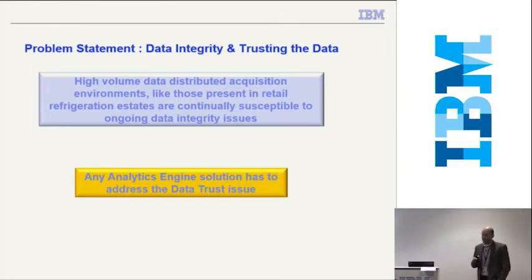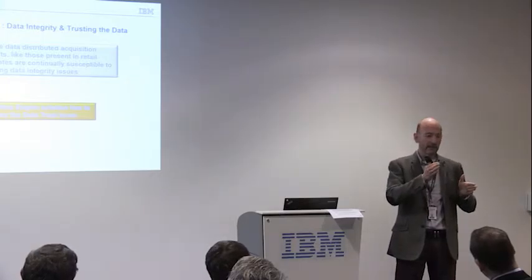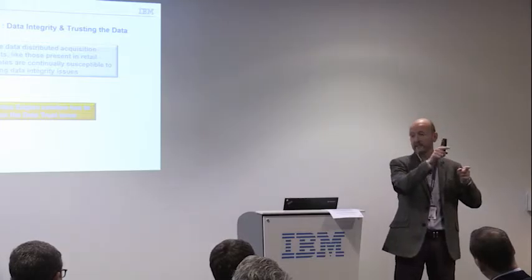Actually, one of the other things that we have as well, just on the data and data outage, another problem that we came across was when you have missing data or data that's bad, what do you do with the gaps? Because you might have analytics that require to look back on this data, and you don't want to have blanks in it, because then you're missing huge chunks of information and insights from that period. So we look at things like, how do we clean the data? So if you have, say, meter data and you're missing, say, a 15-minute period, you might say, well, okay, I have a reading here, I'll just do a straightforward interpolation and say it's the midpoint.